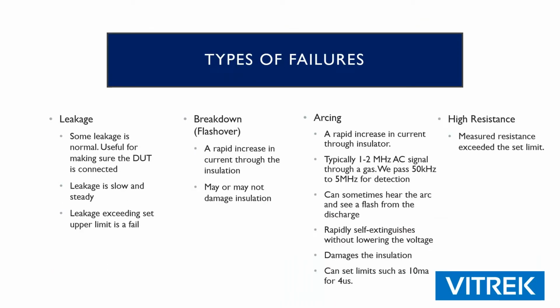All right, so there's a couple different ways you can fail. And there's limits surrounding all of these that can be set up in the tester itself. So the most common is going to be failing leakage. Typically you're going to set a low and a high limit. So let's say you were testing in a range from 1 milliamp to 5 milliamps. If you didn't connect that product at all, you could fail minimum because you would have 0 leakage. And if it was bad, you could exceed that and have 6 or more milliamps of leakage, and then you fail.